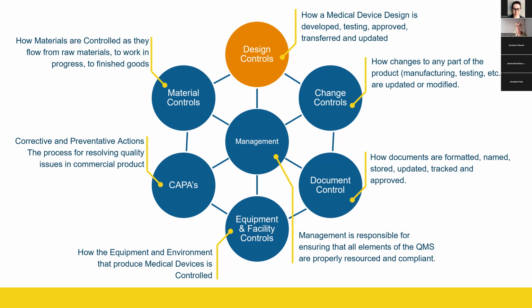Then we have equipment and facility controls. So very important if you are a major manufacturer and you have large pieces of equipment. For example, if you are a medical device sterilization house, you need to make sure that your equipment, whether it's gamma irradiation or ethylene oxide sterilization, all of those major pieces of equipment have vital controls on them that ensure the product is sterilized appropriately.